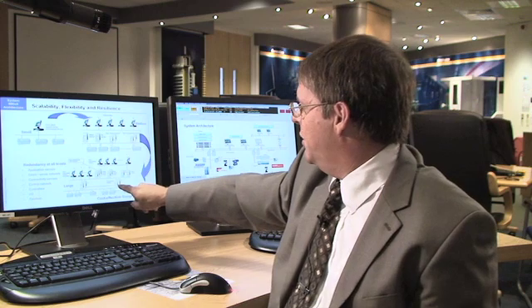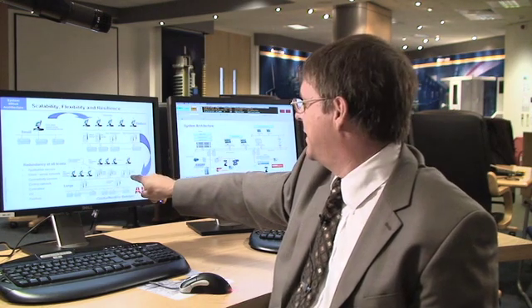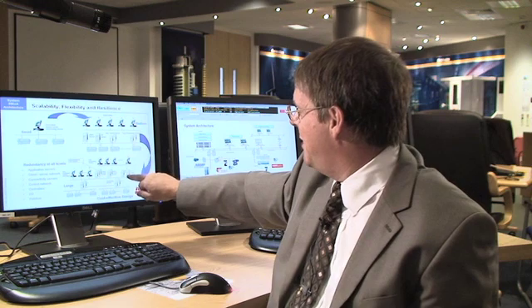I'm then going to add further controllers, redundancy in the specific servers, maybe add an ERP server, maybe add some thin clients for remote control of the application. There you've got full redundancy at all levels — in application servers, client servers, connectivity servers, in your control network, in your controllers and potentially in your I/O and fieldbus.